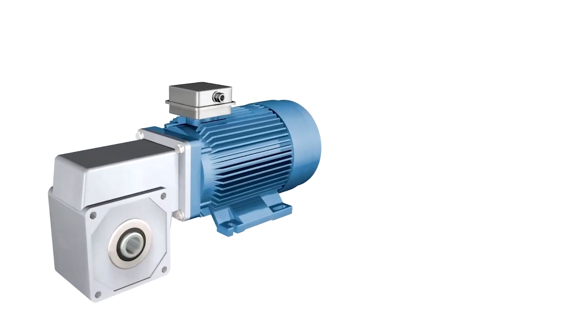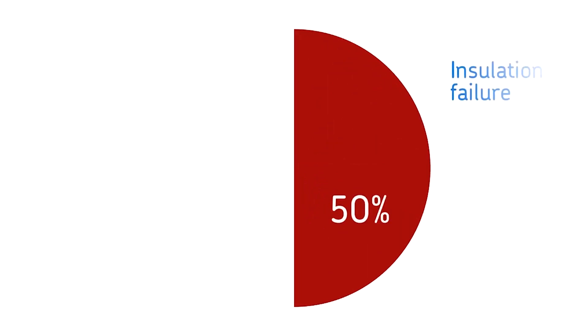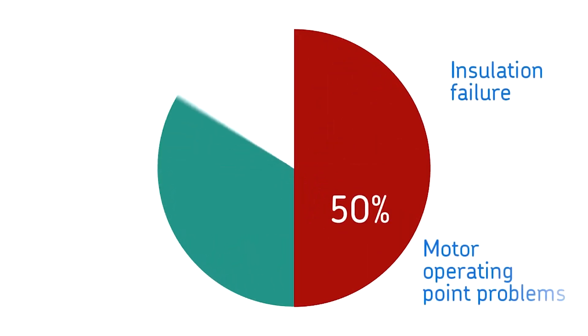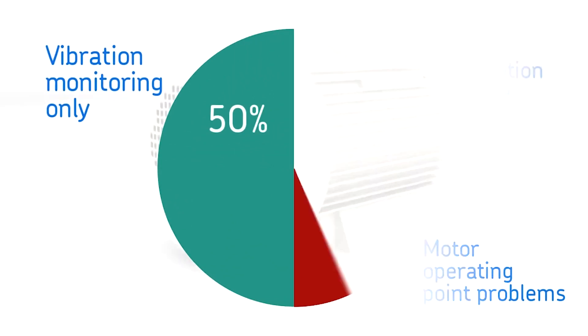Many sites use vibration monitoring on their motors. This is good, but vibration monitoring misses up to 50% of motor failures. These failures are due to insulation failure and motor operating point problems.